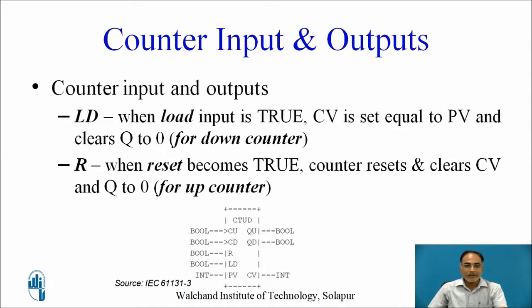The next input is LD, which stands for load. When the load input is true, the CV value is set equal to PV and Q is cleared to 0. The load signal is associated with the down counter. Similarly, R is another input standing for reset. When reset becomes true, the counter resets and clears both CV and Q values to 0. The reset signal is associated with the up counter.